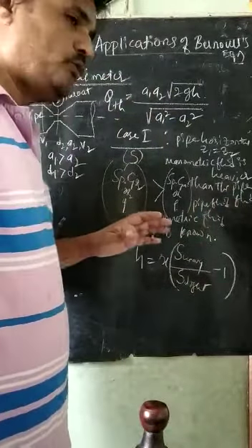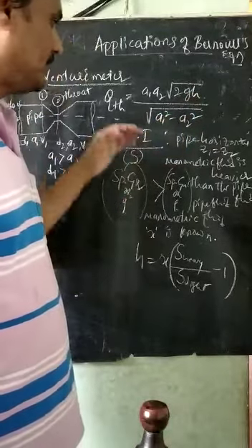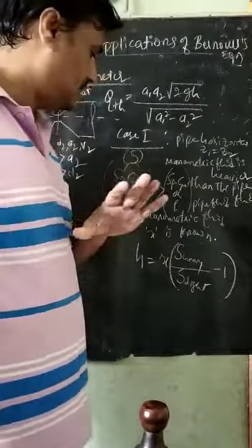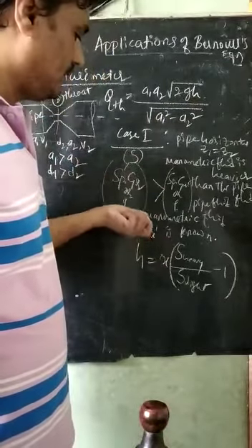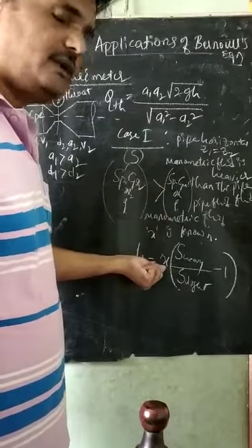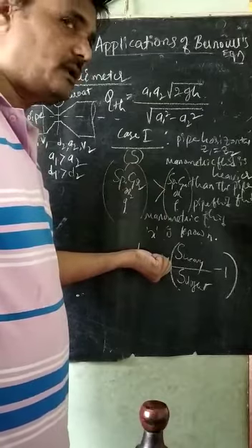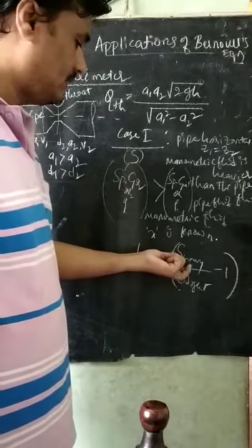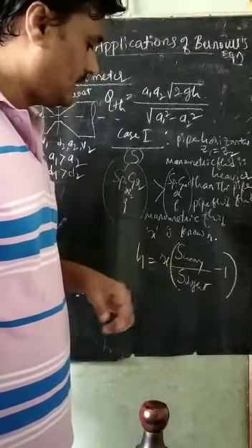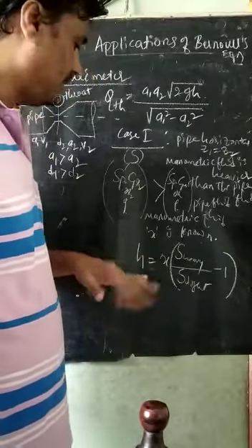So what we need to find is this H value when the pipe is horizontal and the manometric fluid is heavy. We have to take this equation, where X is the difference in the manometric levels, in terms of centimeters here, and S is the specific gravity of the heavier fluid in the manometer, and S light is the specific gravity of the pipe fluid here.